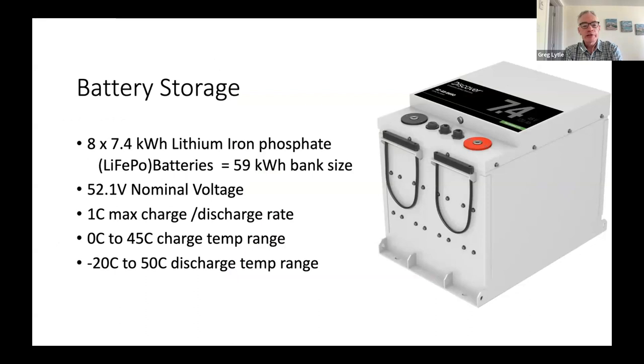One of the most significant updates we've done over the last year was to replace our older lead acid batteries with new lithium iron phosphate batteries. So we've got eight 7.4 kilowatt hour batteries connected in parallel for a 59 kilowatt hour battery bank, with a nominal voltage of about 52 volts. One of the great things about these new lithium batteries is they have really impressive maximum charge and discharge rates, which allow us to really minimize the generator runtime, because you can charge the batteries quickly with a shorter generator operation.